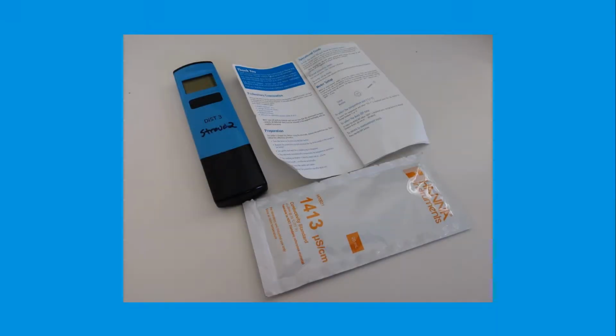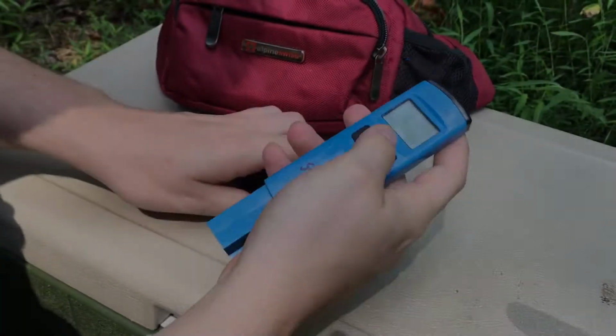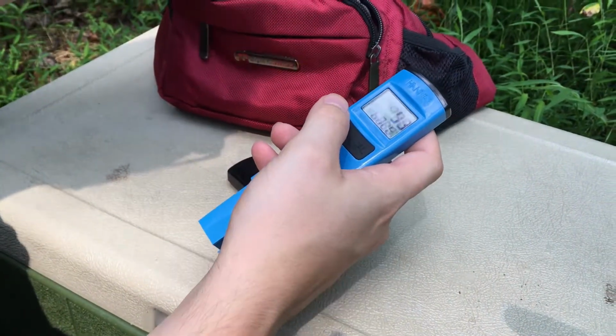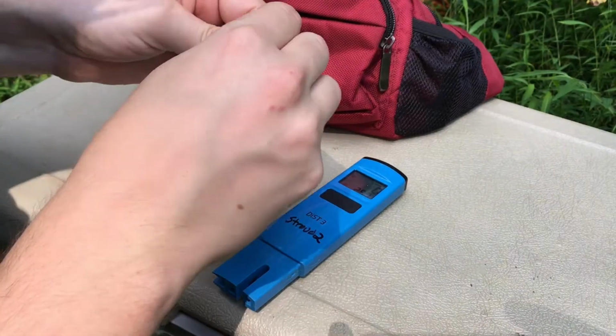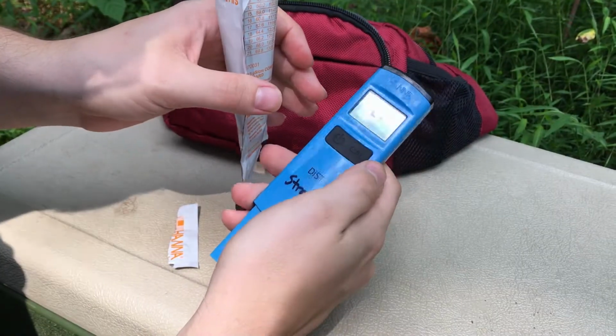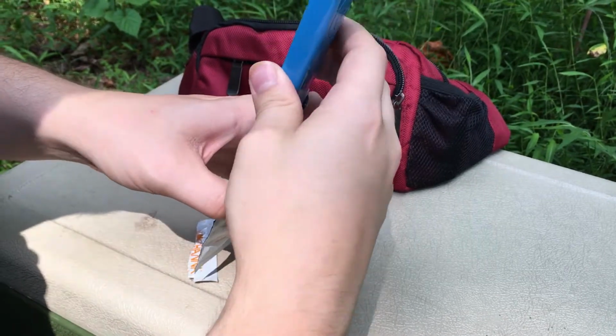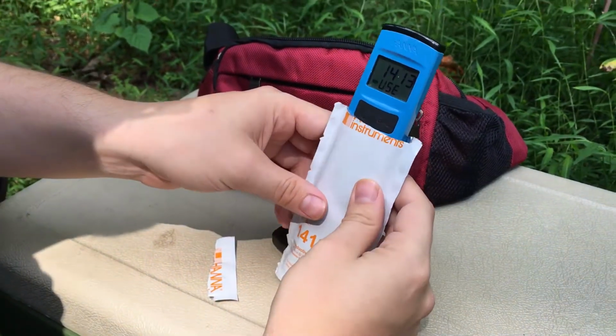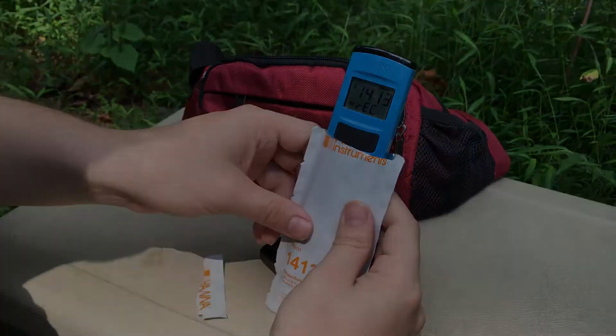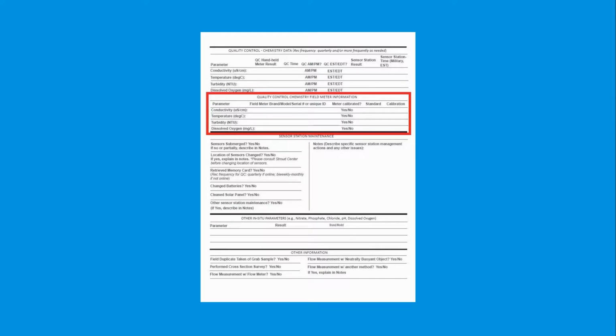In Stroud's Quality Control Kit, we use a HANNA conductivity meter with a range from 0 to 2000 microsiemens per centimeter. This meter is calibrated with a packet of solution that has a known conductivity of 1413 microsiemens per centimeter. We turn on the conductivity meter first. Carefully tear open the calibration packet to prevent spillage. Hit the calibration button on the conductivity meter and lower the sensor ends into the packet. This conductivity meter will automatically calibrate and notify us when the calibration process has been completed. This result is then recorded under the Quality Control Chemistry Field Meter Information section. We then seal the used calibration packet into a Ziploc or pour the fluid into a jar and toss the empty packet into a trash bag.